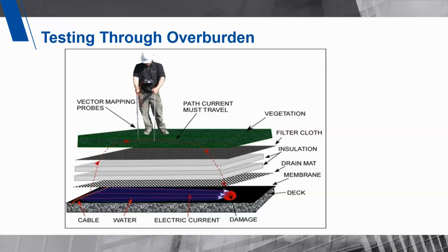But if electrically insulating materials are added above the membrane, it's blocking the circuit. The only way to bridge that gap is with water saturation from the top down. So the further you separate the equipment from the membrane, the more water you need from the top down. So in an extensive or an intensive overburden situation, here's the only way it could possibly even work. That substrate directly under the membrane has to be conductive. Usually it's structural concrete. The membrane itself has to be non-conductive. So it cannot be black EPDM or any membrane containing carbon black.